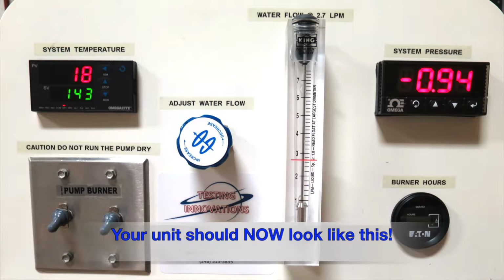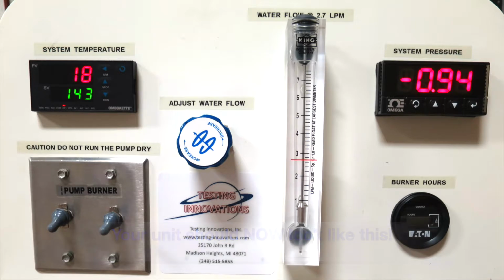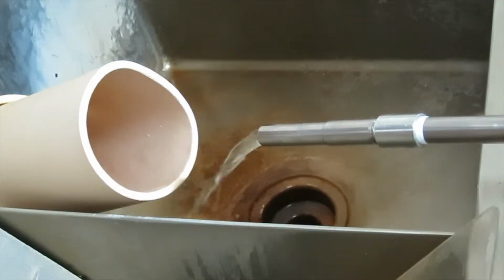If your unit does not closely resemble the unit in the picture, it's time to stop and review all of your connections and hookups. If that doesn't resolve the issue, then give Testing Innovations a call. If you've been successful at getting to this point, you're now ready to turn on the pump. Not the burner, just the pump. You should now visually confirm water flowing out of the end of the wand and verify the water flow rate on the front panel meter in a range between 3.7 and 4.5 liters per minute.